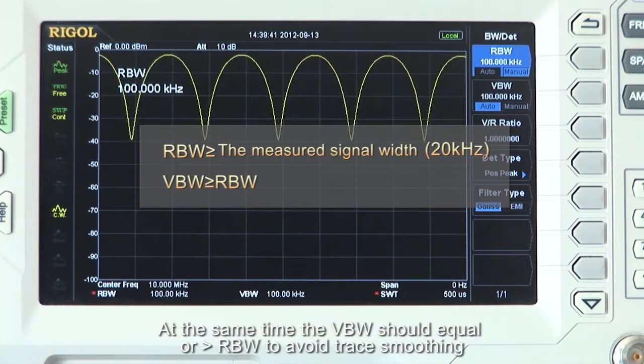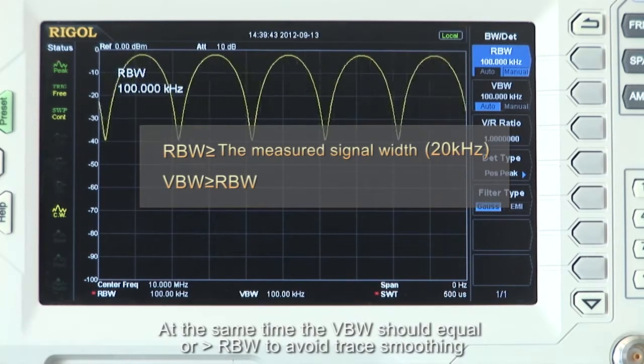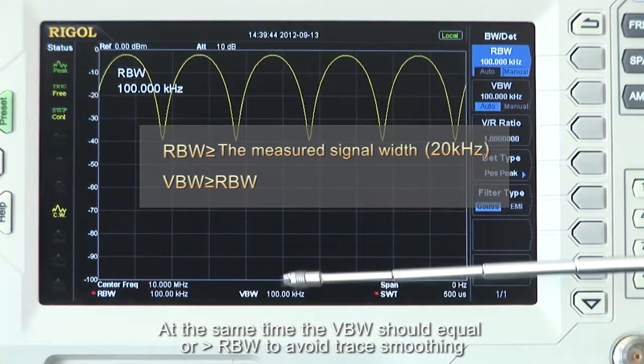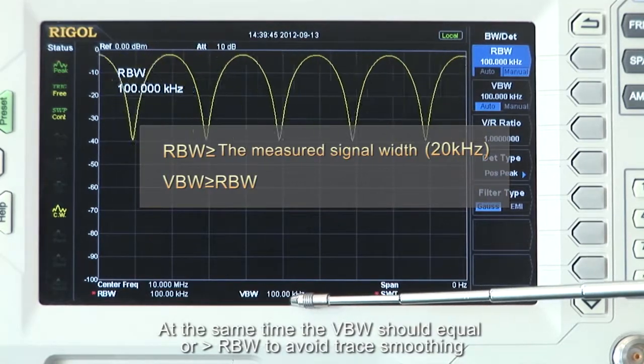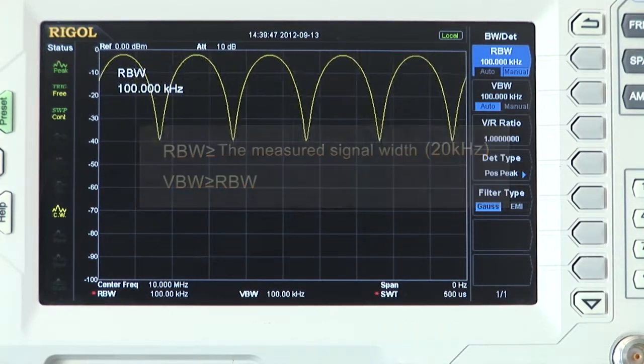At the same time, the video bandwidth, or VBW, should be equal to or greater than the resolution bandwidth to avoid trace smoothing.